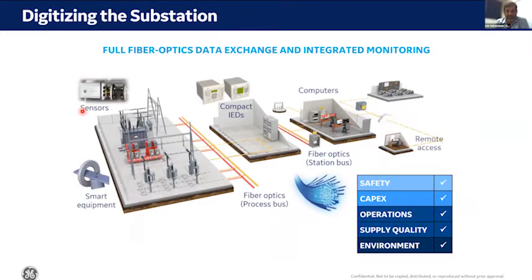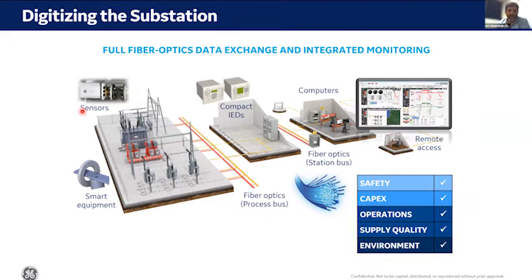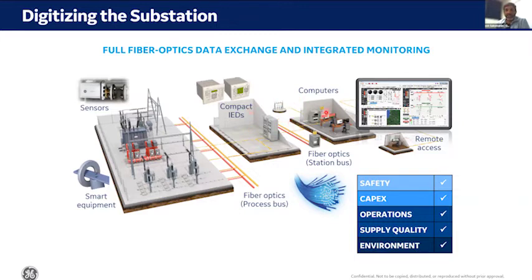This architecture, as seen in previous presentations, shows that from the switchyard the conventional cabling has been replaced by fiber optics. On the switchyard side, smart equipment such as digital CTs/VTs or sensors convert analog values into digital values. In the control and protection room, we have compact IEDs — no need for conventional large-size IEDs with lots of inputs, outputs, and cables. The key difference from a conventional substation is that the cable from switchyard to control room is replaced by fiber optic, with digitization happening at the process side itself.